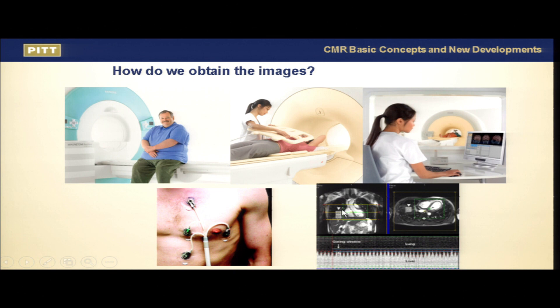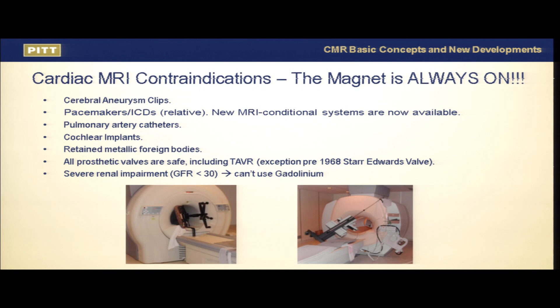A word of caution: the magnet is always on, and we need to respect that. There was a tragic case in India recently in which a patient in a wheelchair was sucked into the magnet — it still happens, unfortunately. There are boundary lines surrounding the magnet that you cannot cross. You cannot turn it off; turning it off would be a huge expense to power back up. Cerebral aneurysm clips are contraindicated, as are pulmonary artery catheters, cochlear implants, and metallic foreign bodies.